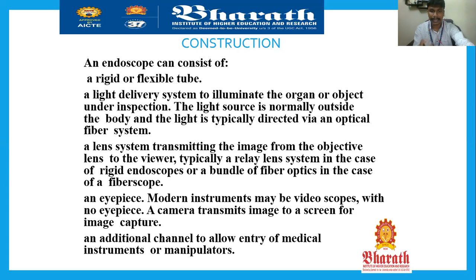A lens system transmits the image from the objective lens to the viewer. This lens system captures the data, and the captured data is sent as an image or a video to the viewer who is watching it on the monitor. Typically a relay lens system is used in the case of a rigid endoscope, or a fiber optic bundle in the case of a fiberscope, for conveying the image captured from the internal organ to the external monitor. Fiber optic applications and rigid endoscope materials are used for capturing the image and displaying it on the display.